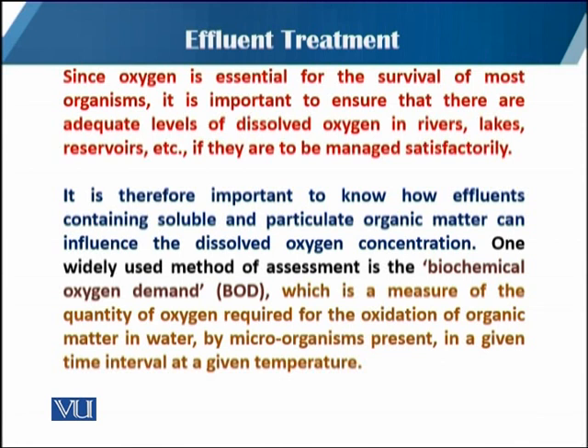One widely used method for the assessment of the pollution level is BOD, which stands for Biochemical Oxygen Demand. BOD is the measure of the quantity of oxygen required for the oxidation of organic matter in the water by microorganisms present, in a given time interval at a given temperature. The level of BOD in our effluent gives the standard of the effluent treatment.